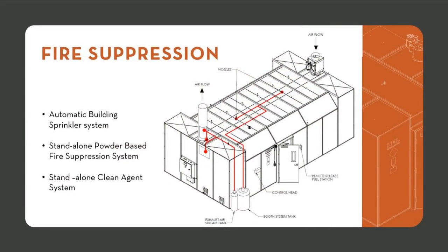Also, another very important part of the room, not as far as how it goes, that's standard with the room, but the reason it's not included in most rooms is because there are various options to go about it. So you can utilize an automatic building sprinkler system. If you have a water-based sprinkler system within your building, you can add extra sprinkler heads and then duct them to a certain area, and then tie into that building panel, again, tie into the control panel on our unit, and then use that sprinkler system for the room.